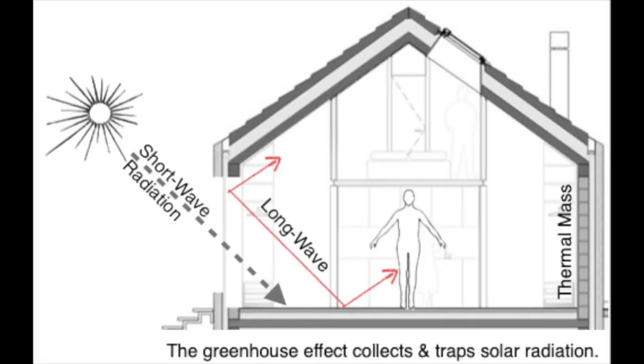Direct solar gain systems. Every south-facing window creates a direct gain system, while windows facing east, west, and north lose more heat than they gain in the winter. The greenhouse effect acts as a one-way heat valve — it lets the shortwave solar energy enter but blocks the heat from escaping. The thermal mass inside the building then absorbs this heat, both to prevent daytime overheating and to store it for nighttime. The proper ratio of mass to south-facing glazing is important.